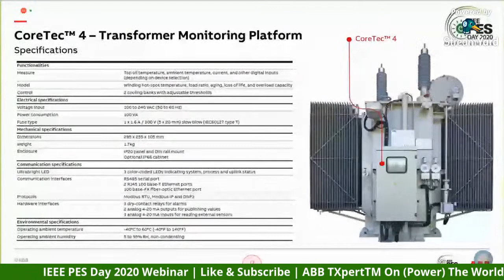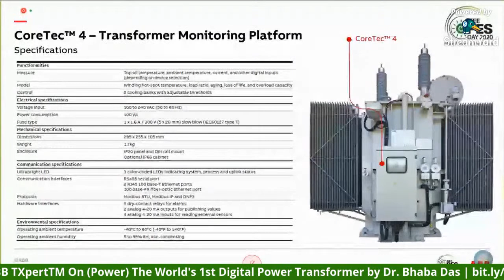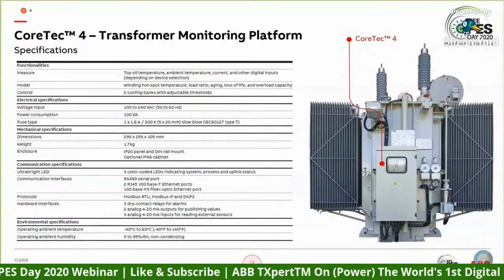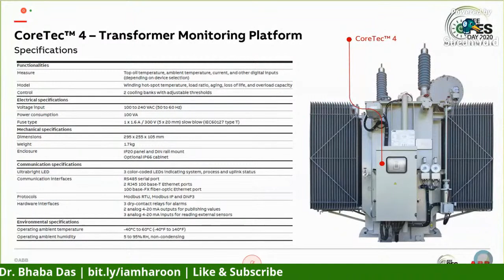So the basic idea is we take the top oil temperature, we take the load data, and then we use the IEC algorithms to calculate what is the winding hotspot, what is the aging rate, what is the loss of life of the transformer. So basically, in every 24 hours, the CoreTec 4 will calculate how many hours out of those 24 hours you have used. And then it will keep on adding up every single day, every year, and you will get a very nice feel of how much you have used the transformer.